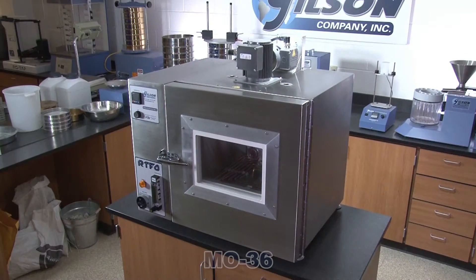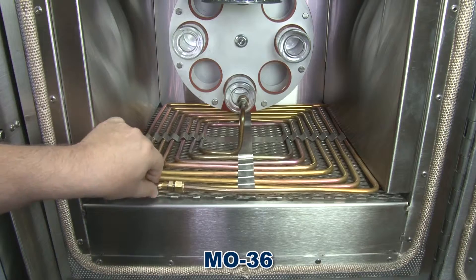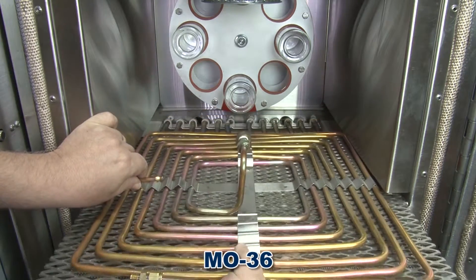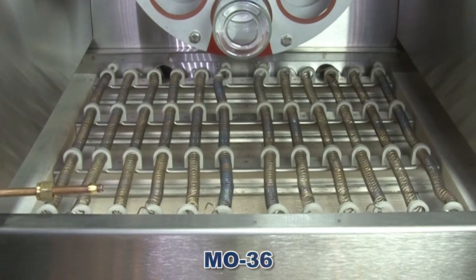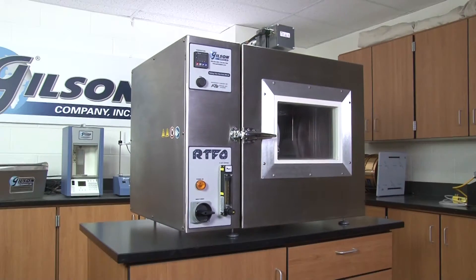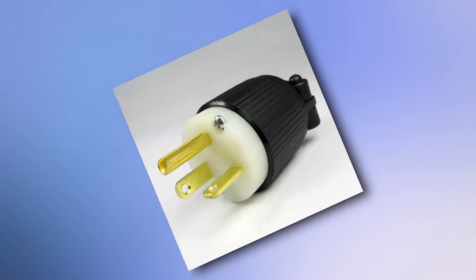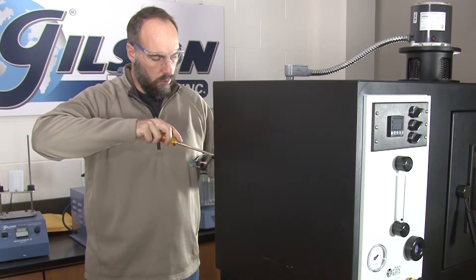The Gilson MO-36 has improved maintenance features such as an easily removable bottom tray, allowing for quick and easy change of heating elements or spill cleanup. The Gilson MO-30 does not. And the Gilson MO-36 has a standard plug-in power cord, while the MO-30 requires an electrician to install its power supply.